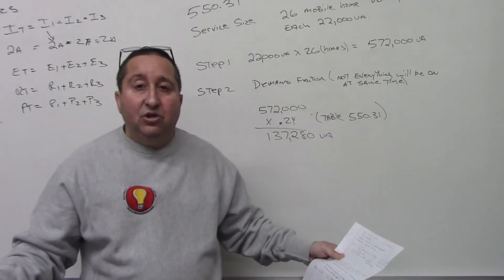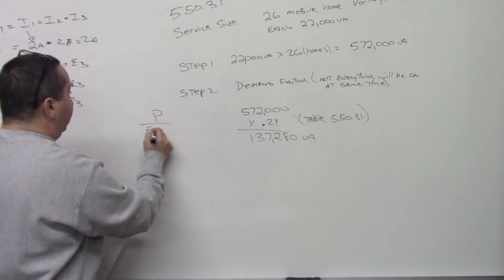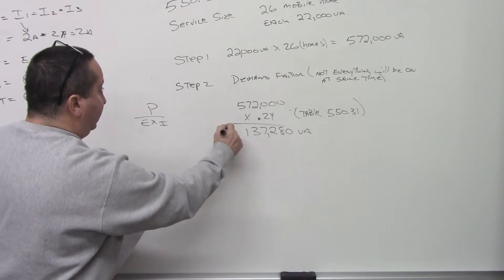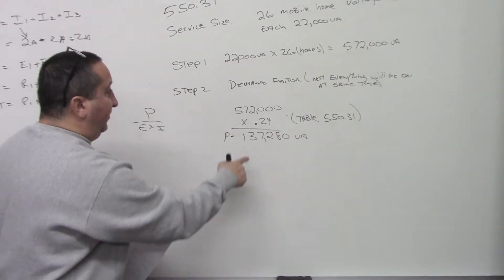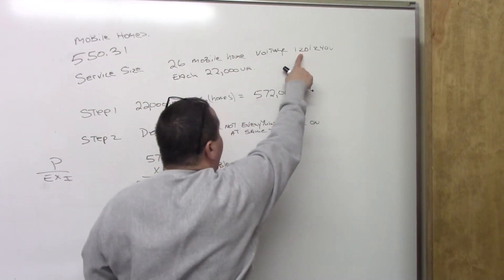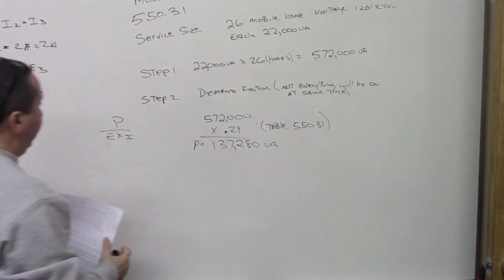And now all you got to do is basic Ohm's law. And here's basic Ohm's law, P equals E times I. We want to find, we got the power, which is volt amps. And we got the voltage, which is 240. You don't use 120. 120 is for the branch circuit. 240 is for the service.